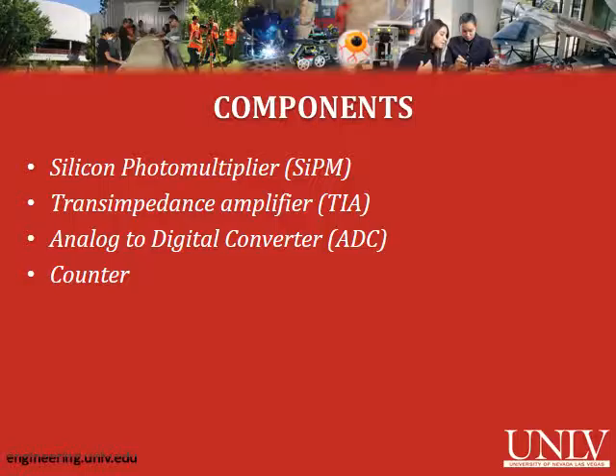The blood sample will flow over the silicon photomultiplier, which will output a pulse when a bacterium flows over it. The transimpedance amplifier, known as the TIA, and analog to digital converter, known as the ADC, will then process the signal to a logic level that will increment a counter. The count of the counter will then display the number of bacteria counted during the trial.